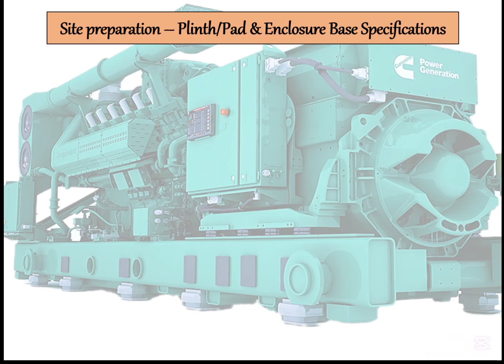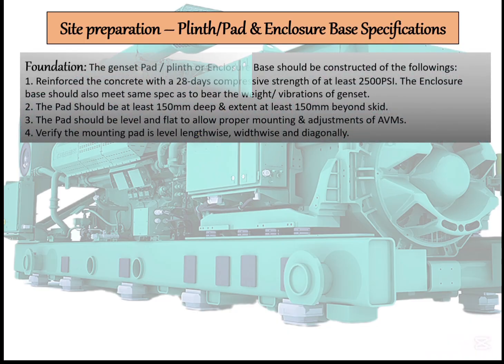The first one is site preparation. Before we receive the genset, our site should be ready to receive it. In site preparation, the first and most crucial part is the plinth, or bed, or enclosure base. The base or plinth should be strong enough to bear the weight of the genset and the vibrations when the genset is in operation. The recommendation is reinforced concrete with a 28-day compressive strength of at least 2,500 psi. So these are the recommendations.